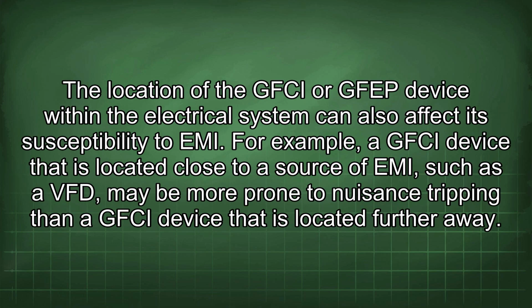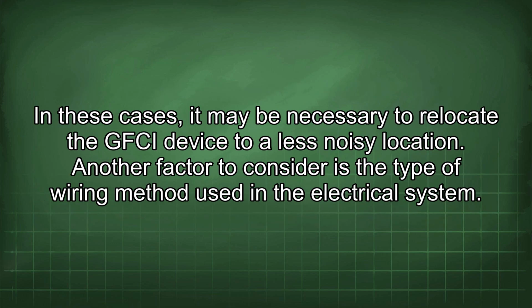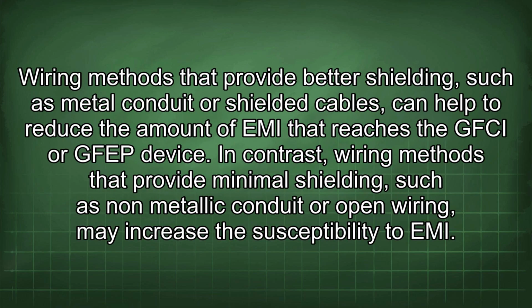The location of the GFCI or GFEP device within the electrical system can also affect its susceptibility to EMI. For example, a GFCI device that is located close to a source of EMI, such as a VFD, may be more prone to nuisance tripping than a GFCI device that is located further away. In these cases, it may be necessary to relocate the GFCI device to a less noisy location. Another factor to consider is the type of wiring method used in the electrical system. Wiring methods that provide better shielding, such as metal conduit or shielded cables, can help to reduce the amount of EMI that reaches the GFCI or GFEP device.